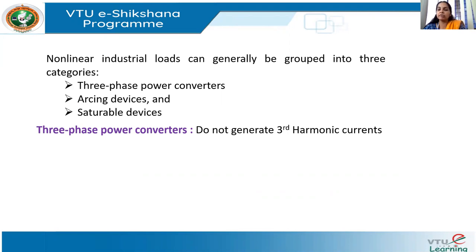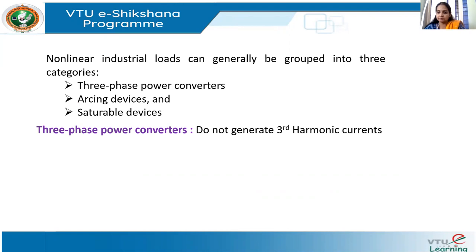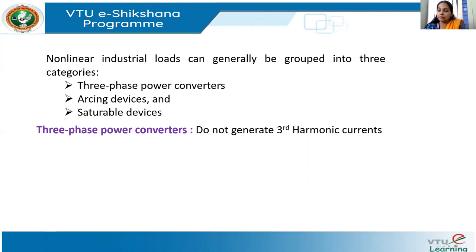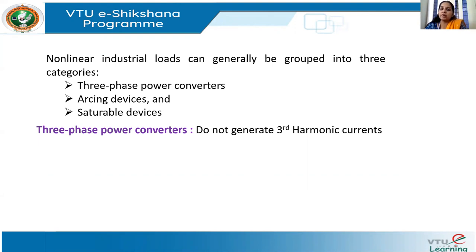In the last class, we saw single-phase power supplies as an example of harmonic sources in commercial loads. What is the difference between three-phase and single-phase loads when talking about harmonics? Three-phase converters differ from single-phase converters mainly because three-phase converters do not generate third harmonic components. This is a major advantage, since most problematic harmonic components include third harmonics. However, three-phase converters still have harmonics from higher frequency components, just fewer compared to single-phase converters.